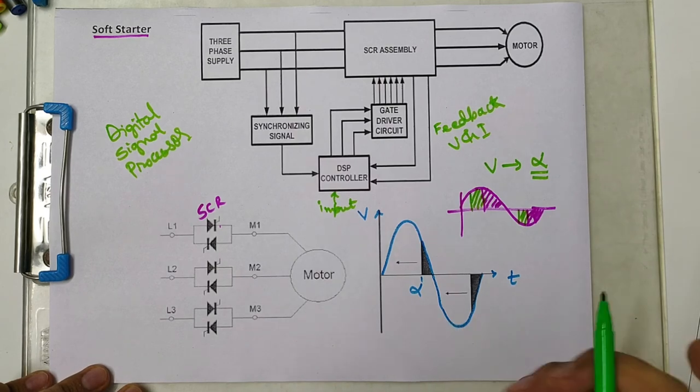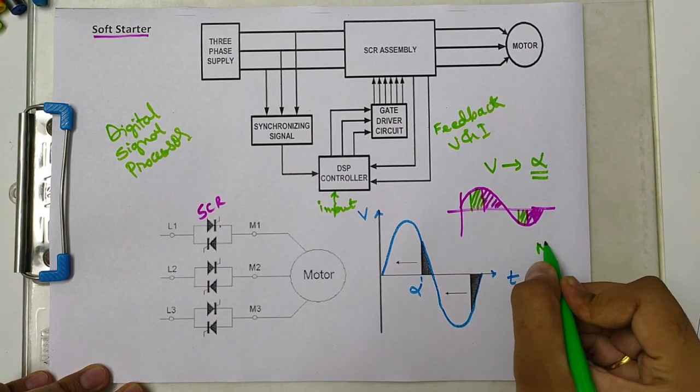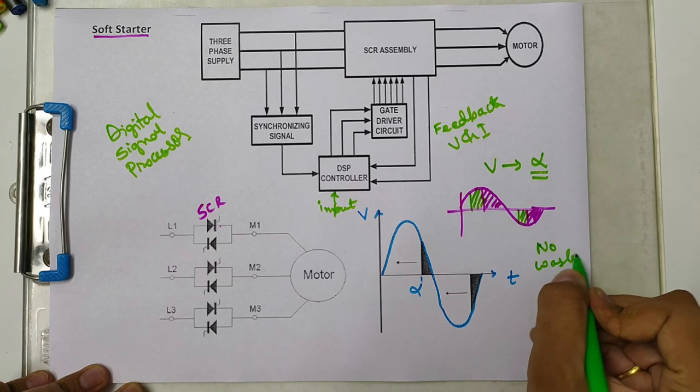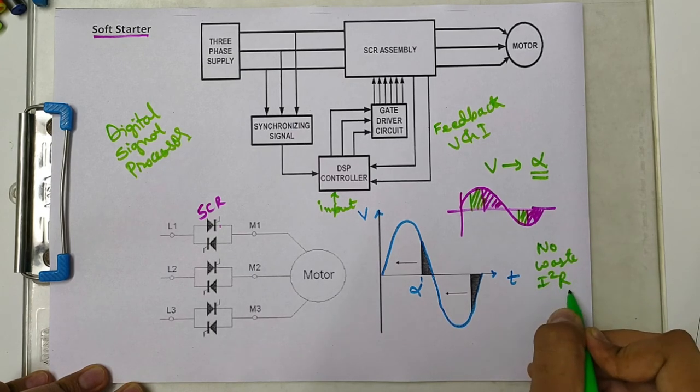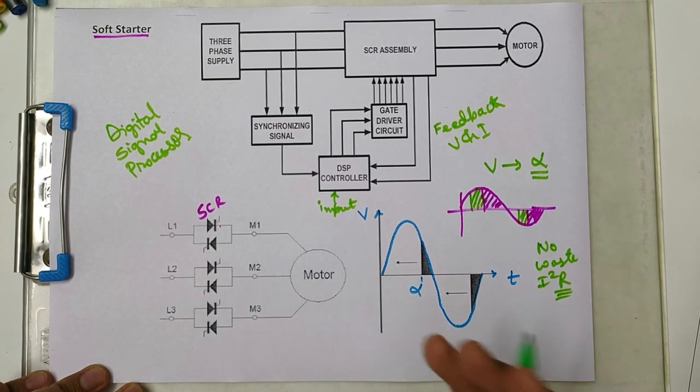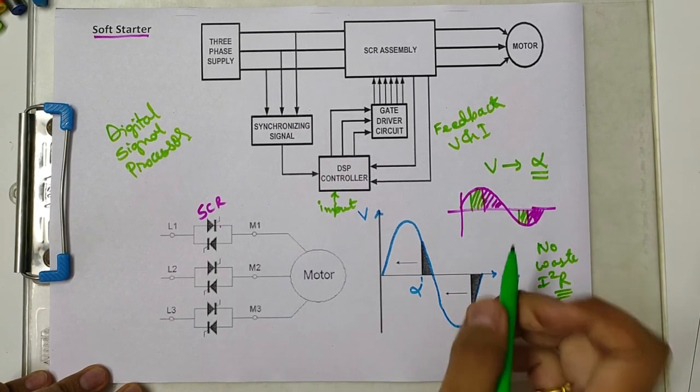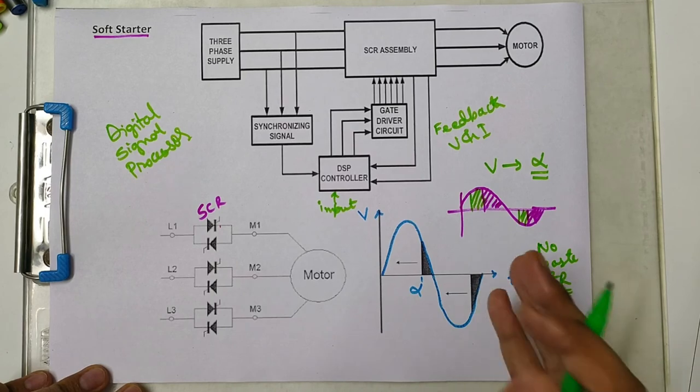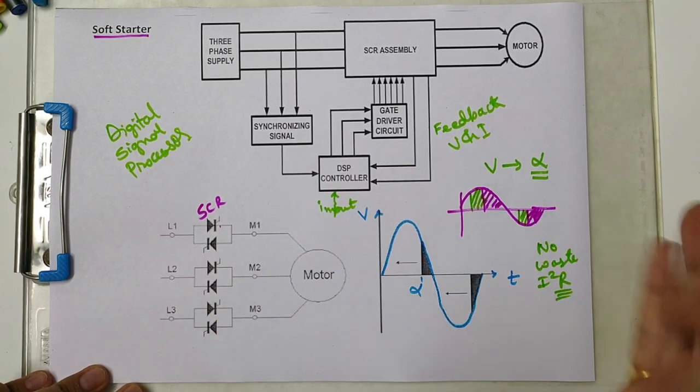Another advantage is that it does not waste energy - no I²R losses. It does not increase resistance to reduce voltage; instead, it cuts the wave from a particular point, so energy is not wasted and excess energy is not supplied to the motor.